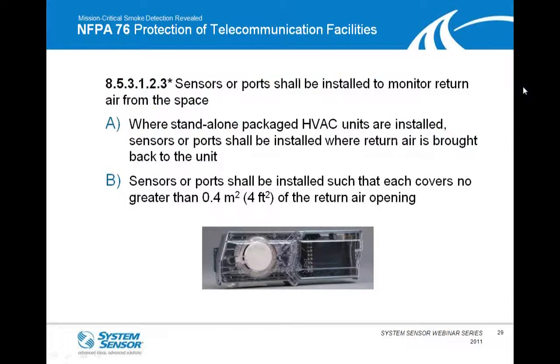Additionally, 8.5.3.1.2.3 calls out that sensor ports shall be installed to monitor return air from the space. So here again, if that air is leaving, which, in order to maintain the air changes and keep the equipment cool, a lot of air changes typically have to occur, it does require that you monitor the return airspace from that space. And in A, it talks about where standalone packaged HVAC units are installed. Again, ports shall be installed where the return air is brought back to the unit, such that each covers no more than 4 square feet.